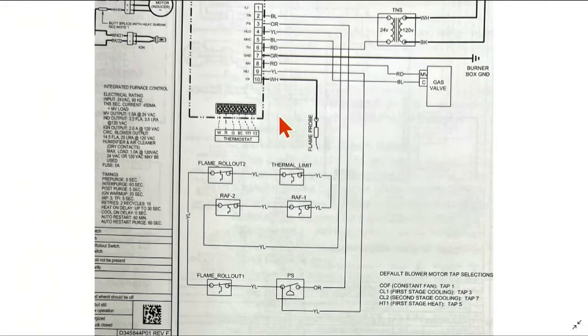Gas valve shuts. Most often when a fault occurs, the blower will run to clear out any excess heat. But again, filters clogged, registers closed, blower stops, any kind of air obstruction, and there's excessive heat built up in the heat sequence, and these switches open, then it'll stop the sequence. Now, we're going to use a very recent diagnostic to show how to diagnose an open switch, how to test an open switch, and maybe reset an open switch due to heat activation. Let's take a look.